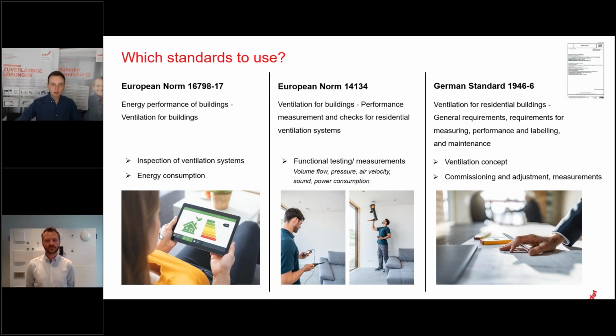Then we have the German standard DIN 1946 Part 6, which is the one we use to plan and design our ventilation systems. It is made for residential purposes and includes all requirements, from planning and creating a ventilation concept, to design and calculating volume flows, to carrying out commissioning, measurements, and maintenance at ventilation systems. This is a central standard for residential ventilation.